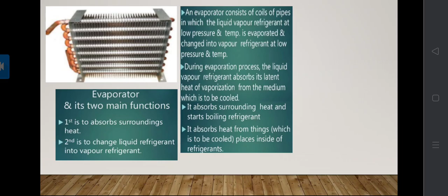So the evaporator consists of coils of pipes in which liquid-vapor refrigerant at low pressure and temperature is evaporated and changed into vapor refrigerant at low pressure and temperature. Also, during the evaporation process, the liquid-vapor refrigerant absorbs heat, its latent heat of vaporization, from the medium which is to be cooled. So it absorbs surrounding heat and the refrigerant starts boiling, and it absorbs heat from things which are to be cooled and placed inside the refrigerator.